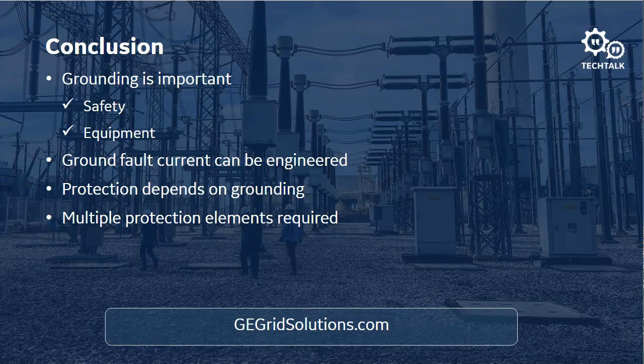And not only when the generator is running, but when the generator is not even running, we can still inject that subharmonic voltage and be able to detect ground faults even when the generator is not running. So it gives us a heads up before we start running the generator: hey, there's a ground fault already on there. We need to look at it before we start the generator.